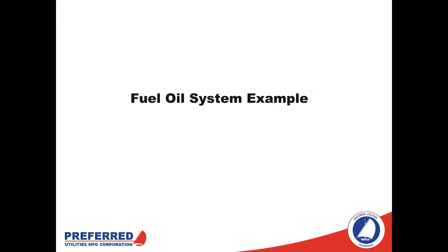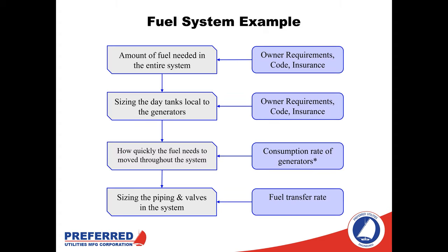Let's take a look at a fuel oil system example. If we have a new project, where do we start, and how do we get the ball rolling from a blank piece of paper? Typically, we'll begin with the amount of fuel needed in the entire system — this can be dictated by the owner, by code, or insurance. Then we'll size the day tanks local to the generators, then look at how quickly fuel needs to move throughout the system by sizing the pumps based on the consumption rate of the generators, with a very important caveat we'll cover shortly.